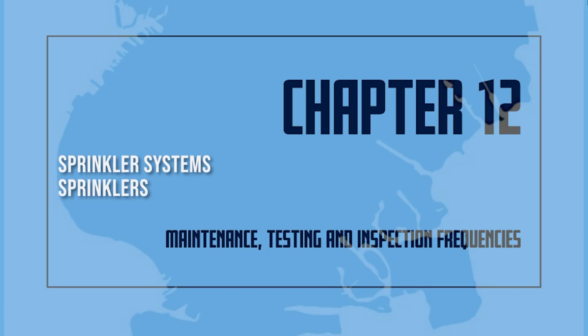If the above problem occurs, the sprinkler shall be replaced. Glass bulb sprinklers shall be replaced if the bulbs have emptied. Unacceptable obstructions to spray patterns shall be corrected. Sprinklers installed in concealed spaces, such as above suspended ceilings, are not required to be inspected. Sprinklers installed in areas that are inaccessible for safety considerations due to process operations shall be inspected during each scheduled shutdown.